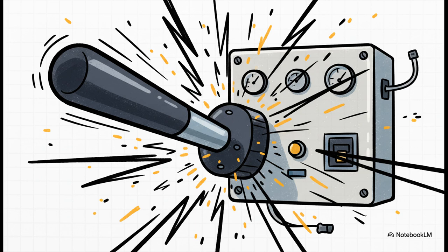Because the physics here are just totally unforgiving, our control systems are built to be absolutely ruthless. Modern grids are constantly monitored by SCADA systems and protective relays, like the ANSI 81. These things must be explicitly programmed for the exact base frequency of the region. If a 50 Hz programmed relay even briefly monitors a 60 Hz system, it registers that frequency as a critical system-ending anomaly and commands an instant trip, shutting down the entire system to protect it. There is literally zero margin for error.